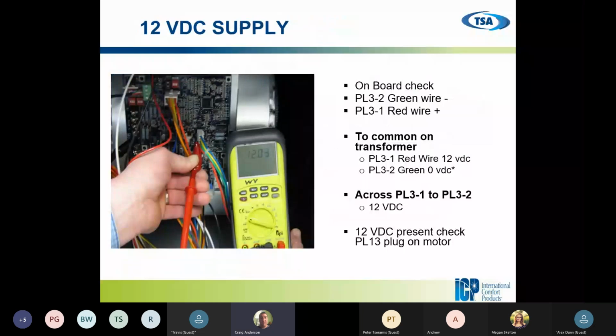So 12 volt DC supply, we're going to have going to our motor. We know we have our 110 going on our black and white. That's present at all time. We're looking for a DC voltage now on our green and our red. So we want to check both terminals. We want to check our red to ground. We want to check our red to common. We want to make sure we're getting the same voltage. We should have 12 volts DC constantly at all times. These voltages should not be fluctuating.